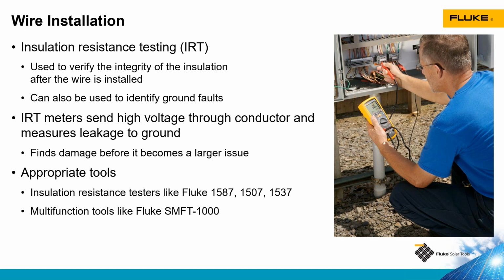And finally, we have the SMFT 1000. This is a solar multifunction tool. It is capable of doing all of the tests required by this IEC standard, including insulation resistance testing. A unique feature of the SMFT 1000 is that it will do a regular point-to-point test of your string of modules. It will test from positive to ground and negative to ground, and give you the lowest insulation resistance value of the two.